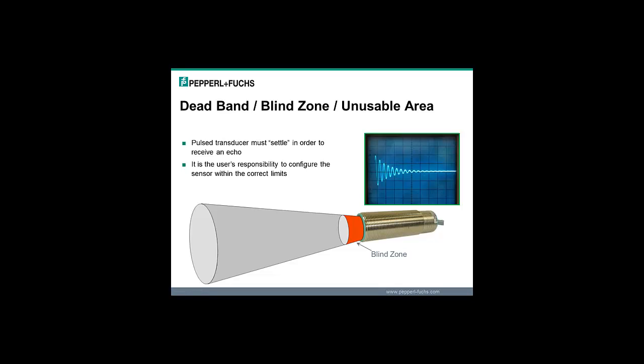So here's a graphical illustration, maybe an oscilloscope illustration, of what's going on when an ultrasonic sensor transducer is struck and creates its evaluation pulse. The transducer, as I mentioned in the previous slide, must settle before it receives an echo. So you have that area where it's just really too close. The sound comes out, hits a target, and comes back to the transducer while it's still ringing, and it can't determine what's going on because it needs to settle before it can listen. It is the user's responsibility to configure the sensor within the correct limits. The sensor won't know if you're in the blind zone or not because it's still ringing. It has no idea what's going on.